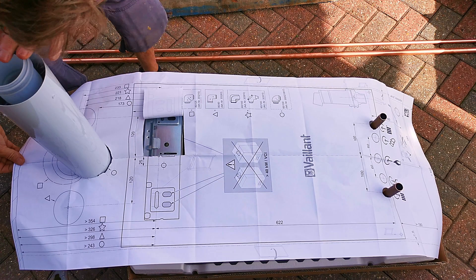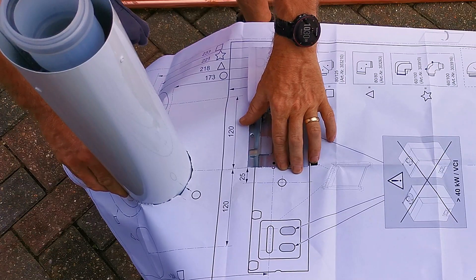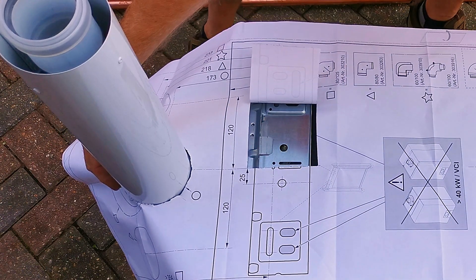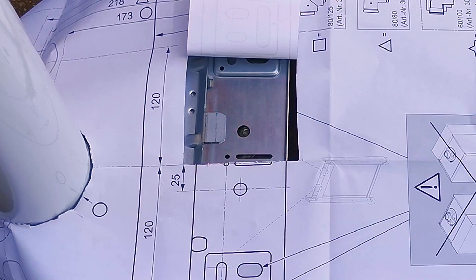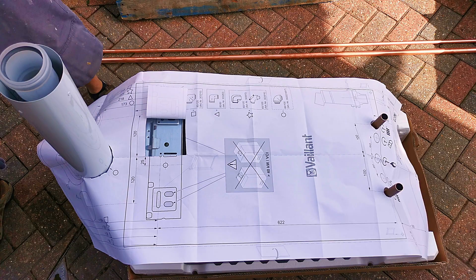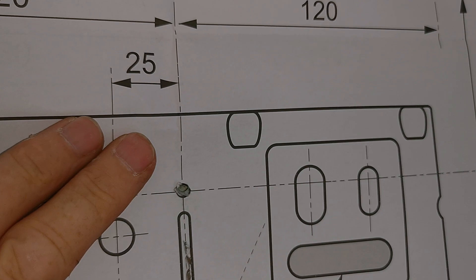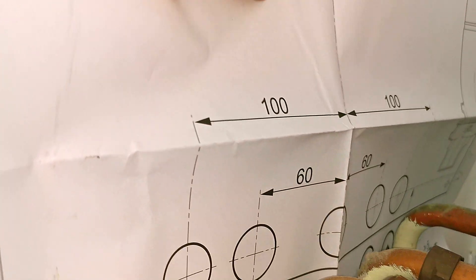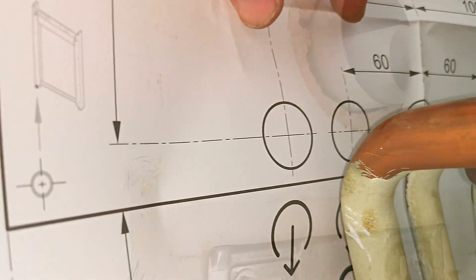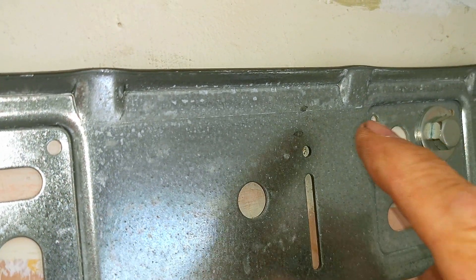On my third install of this boiler I did check the template, because I remembered many years ago the ecomax template was out by a little bit. But you can see that this new template lines up perfectly with the flue bracket and the pipes on this brand new ecoTEC plus 836. So when you replace an old ecoTEC boiler with one of these new ones, if you get the same issues let us know in the comments what you did to correct it, or whether my second install was just some kind of weird anomaly.